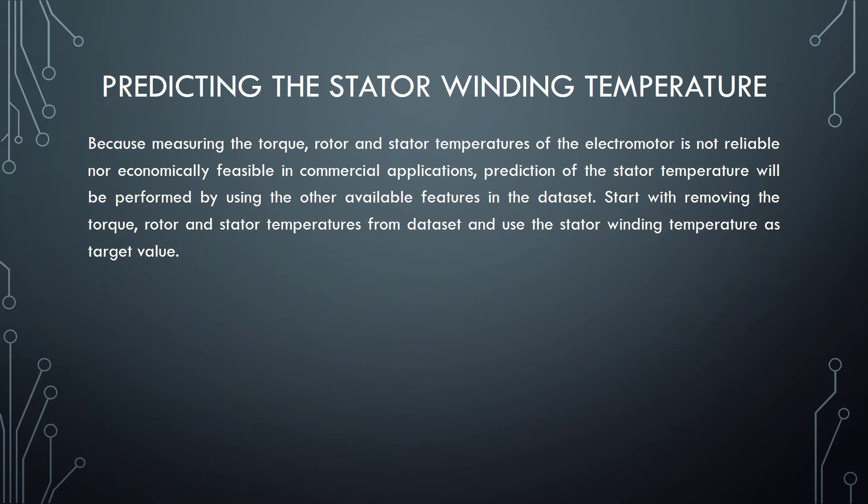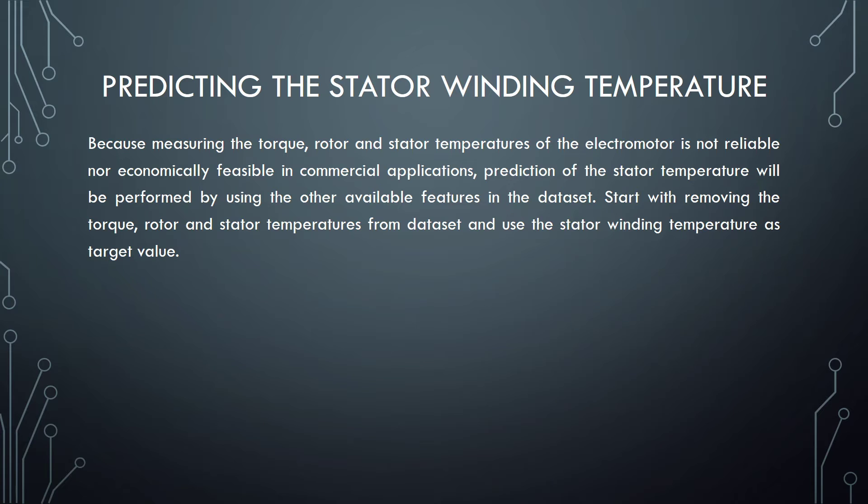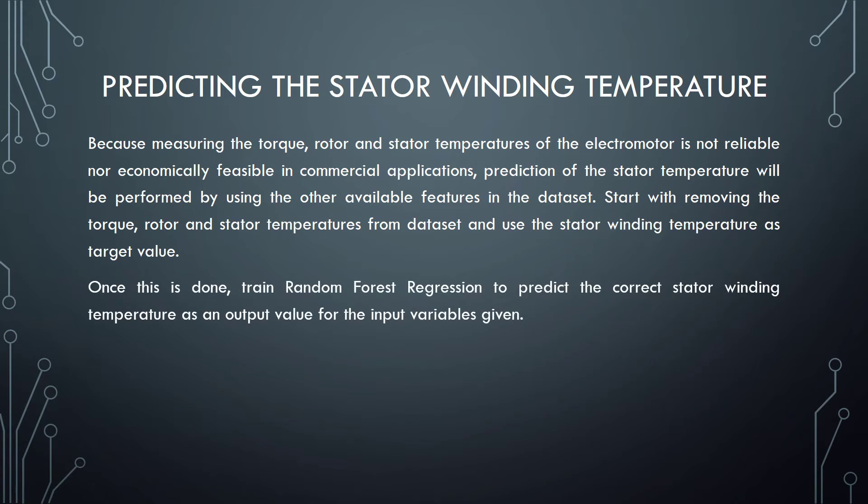Predicting the stator winding temperature. Because measuring the torque, rotor and stator temperatures of all electric motors is not reliable nor economically feasible in commercial applications, prediction of the stator temperature will be performed by using the other available features in the dataset. Start with removing the torque, rotor and stator temperatures from dataset and use the stator winding temperature as target value. Once this is done, try random forest regression to predict the correct stator winding temperature as an output value for the input variables given.